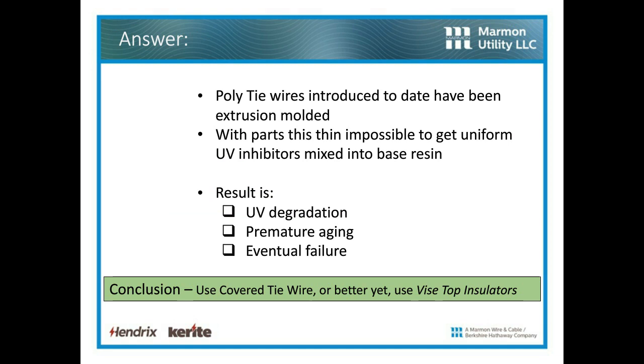So poly tie wires introduced to date have been extrusion molded. Obviously, how else are you going to make them? With parts this thin, it's impossible to get uniform UV inhibitors mixed into the base resin. So the result is UV degradation, premature aging, and eventual failure. They're going to fail mechanically. So the conclusion is to use covered tie wire. It's simple. Or better yet, use Vise Top insulators.